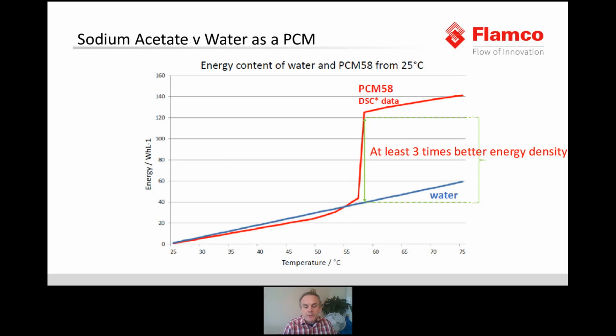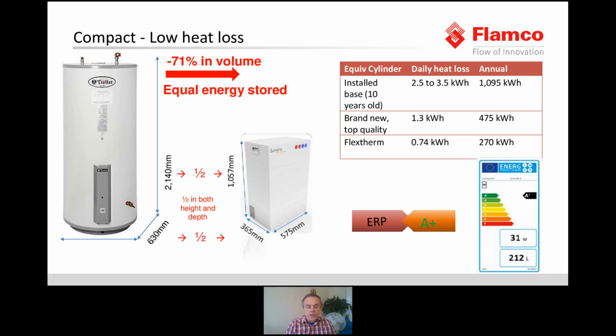In this graph, you can see the difference between the energy density of water compared to the PCM 58 when you use it in a heat battery. As shown on the graph, at 58 degrees Celsius, the energy density of the PCM is a minimum of 3 times better than water. This explains why a heat battery is so compact and still has the same hot water volume as a much larger hot water storage vessel. So visually, the battery is a much reduced total volume. It's 71% compared to a 300-litre storage vessel with equal energy output.